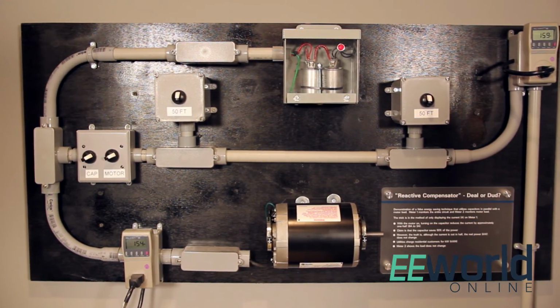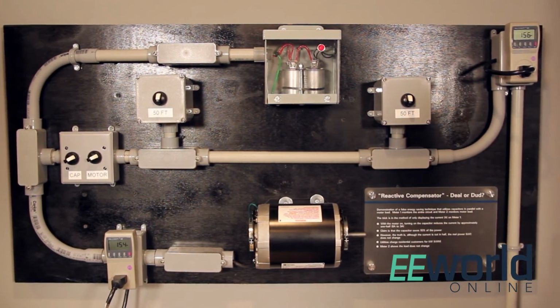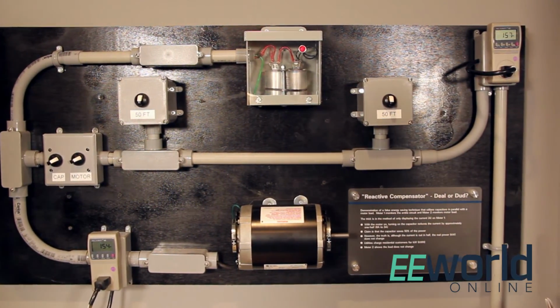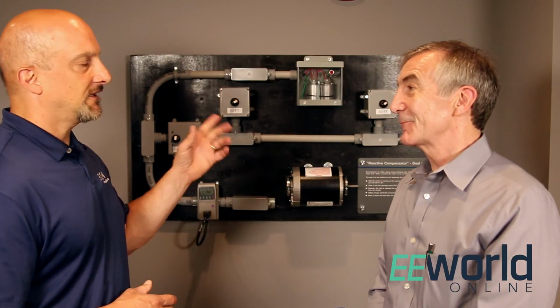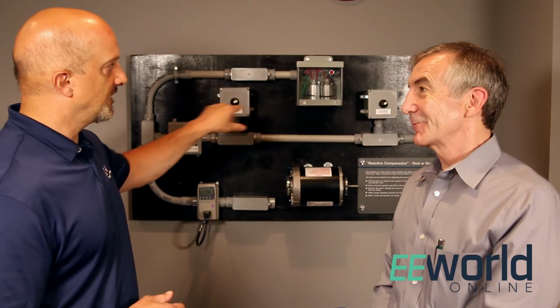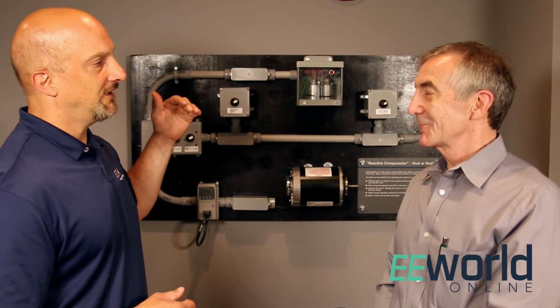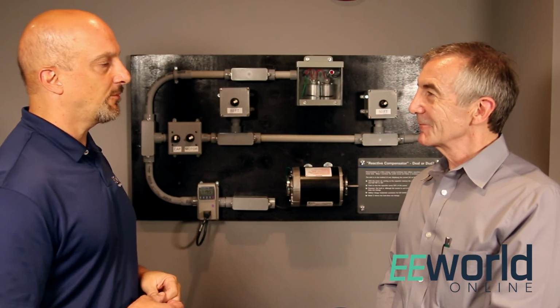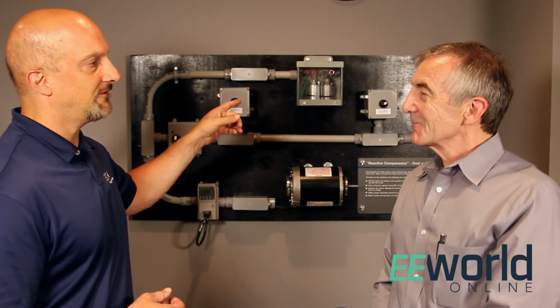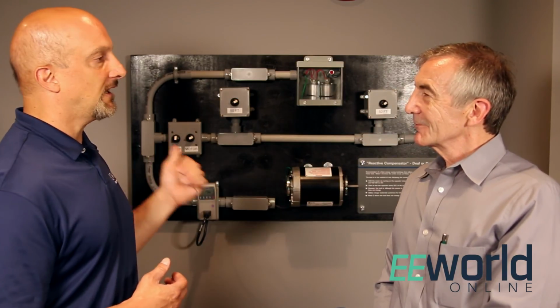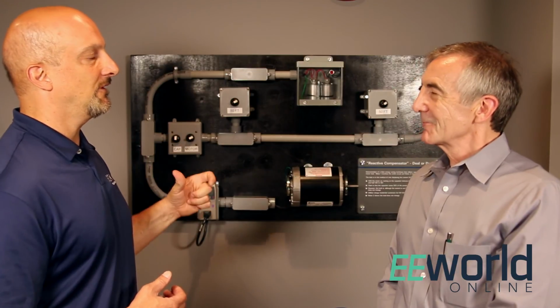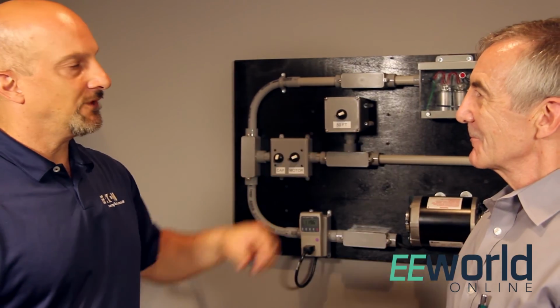So just so we're clear, the losses you're seeing there are the I squared R losses, not the losses from additional inductance from that wire switched in. No, it's exactly that. It's the resistance of the wire times the current, and if we reduce the current, because again, current and VA or kVA are proportional, so we reduce the current by putting the capacitor in. What happens is we reduce the I squared R losses. Again, it's current squared, so it does make it look like it's a big deal. But again, it's really these little tricks that they'll do, and it's unfortunate because it will make people think that it's real in their system.